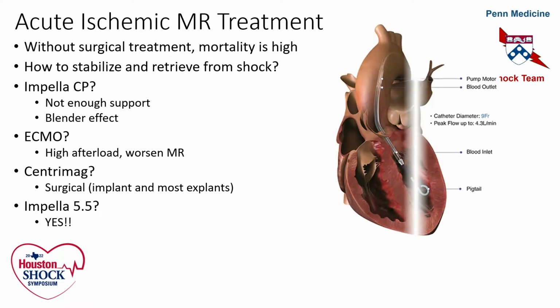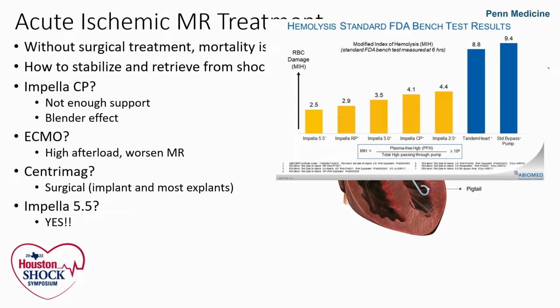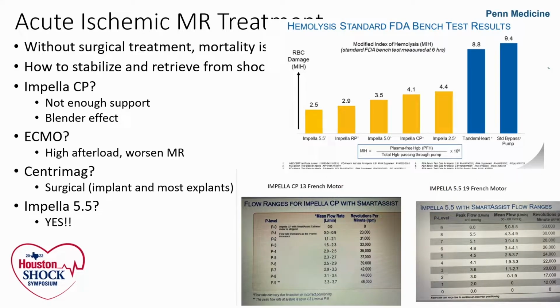An Impella CP? Not enough support likely, because this data shows, in the middle yellow block with the 4.1 above it, that the Impella CP has a higher risk of hemolysis, red cell damage, compared to our larger pumps. You can see here that the motor's smaller on the bottom left graph, so you need to run at about 43,000 RPMs to achieve 3.5 liters of flow, versus with a 5.5, you can get up to 6.2, 6.7 liters of flow at RPMs of 33,000.